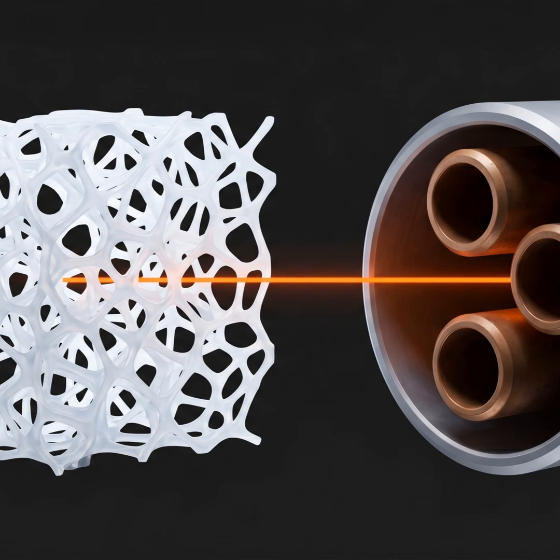OEMs generally dislike third-party desuperheaters being attached to their equipment, because of warranties, liability, and fluid dynamics. If a contractor splices a third-party heat exchanger into the discharge line of a massive, highly calibrated chiller, it introduces a slight pressure drop and marginally changes how the fluid moves through the system.